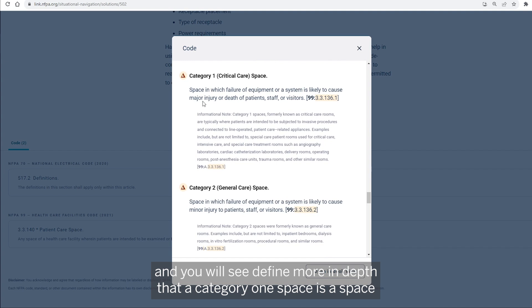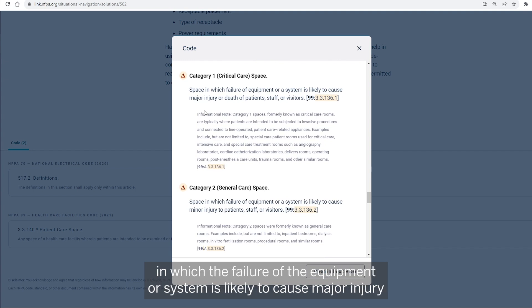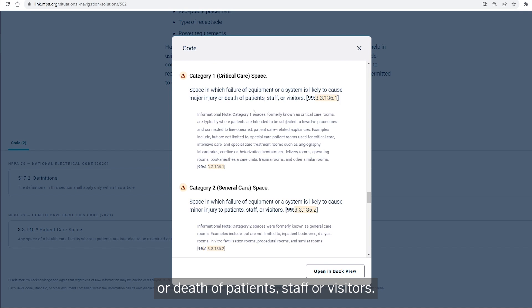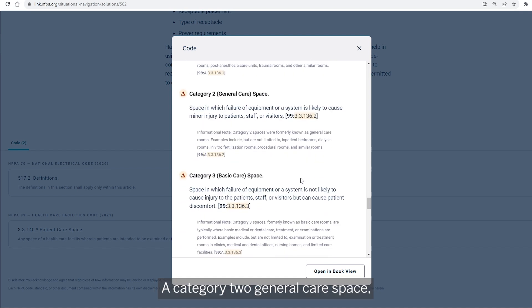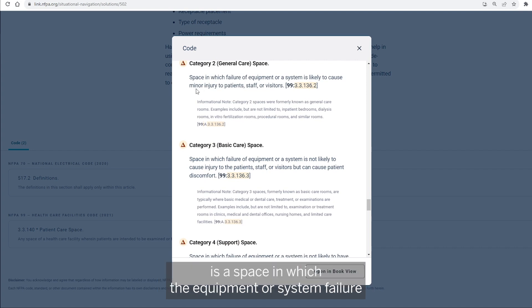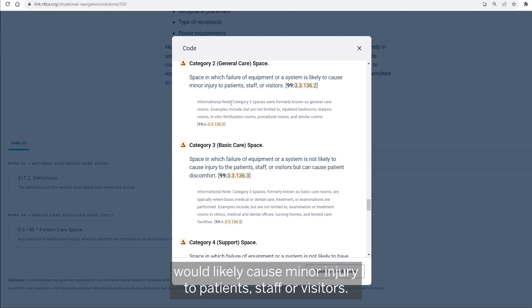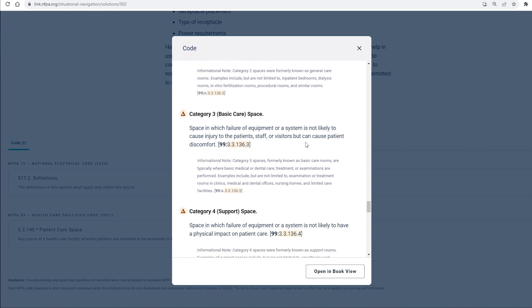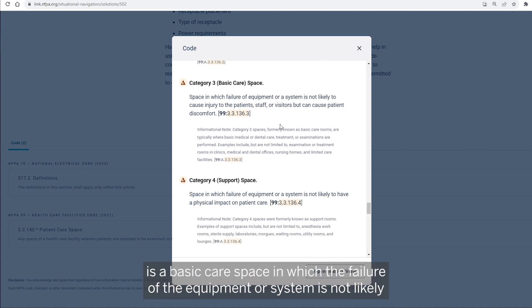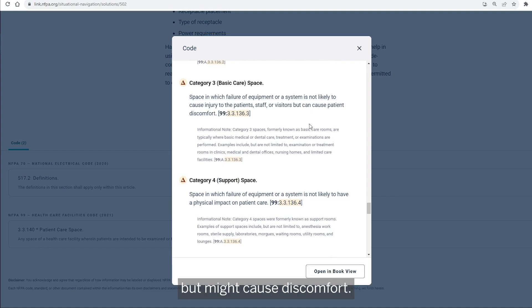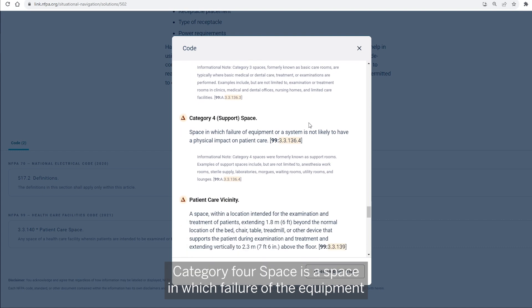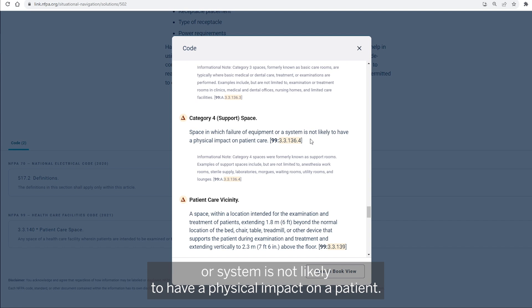You will see that a category one space is defined as a space in which the failure of the equipment or system is likely to cause major injury or death of patients, staff, or visitors. A category two general care space is a space in which equipment or system failure would likely cause minor injury to patients, staff, or visitors. Category three is a basic care space in which failure of the equipment or system is not likely to cause injury but might cause discomfort. Category four is a space in which failure of the equipment or system is not likely to have a physical impact on a patient.